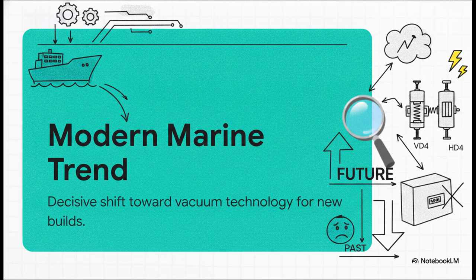Taking a step back, this whole split perfectly illustrates a massive shift in the broader industry. The modern marine trend is a decisive move straight toward vacuum technology. If you're commissioning new build tonnage today, you're almost always going to be working with vacuum instead of SF6. Vacuum interrupters, like the ones in the VD4, are super efficient, quick opening, and essentially maintenance-free. Meanwhile, SF6 gas has amazing heat transfer properties but needs careful handling because of sour-smelling decomposition byproducts after an arc, and it's hanging on only in the HD4 model as far as current production goes. The industry has clearly spoken, and vacuum is the standard moving forward.